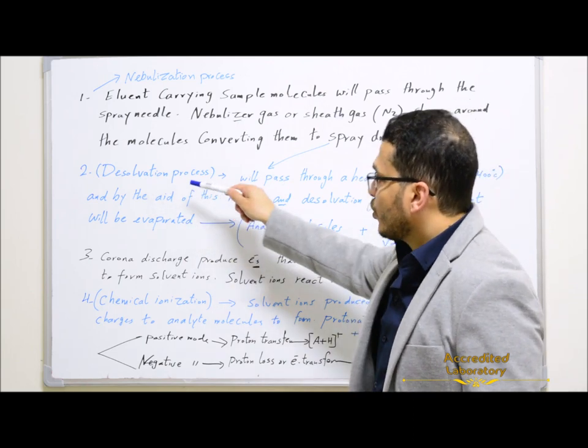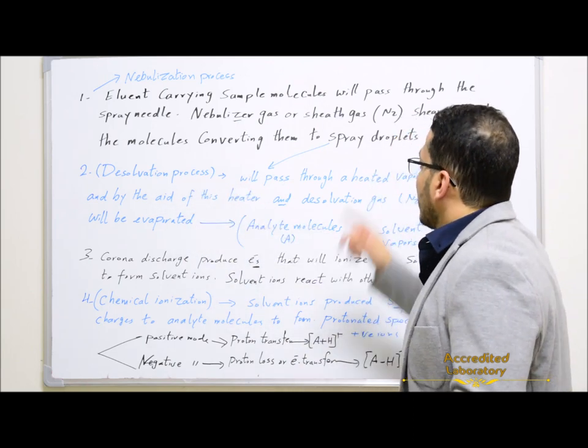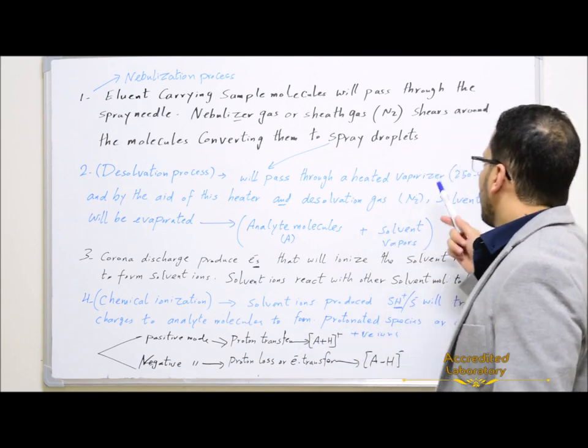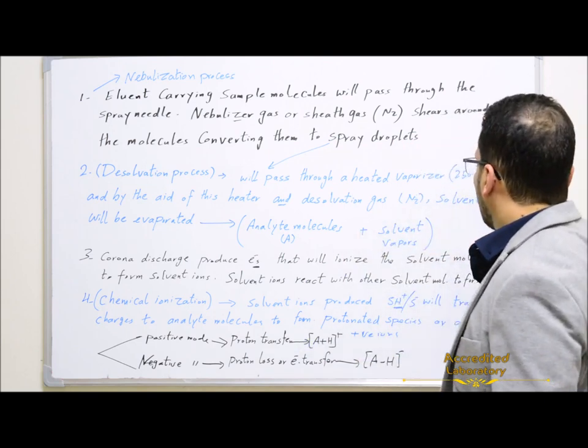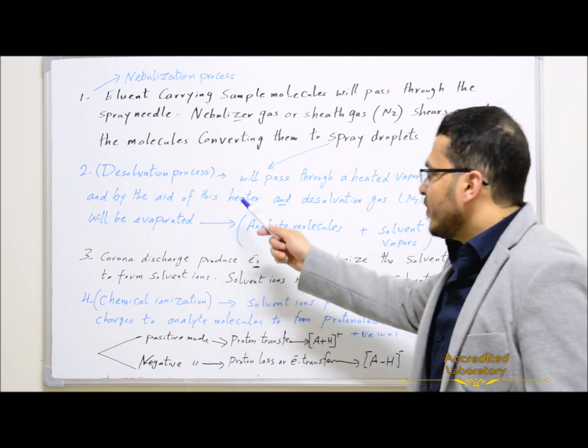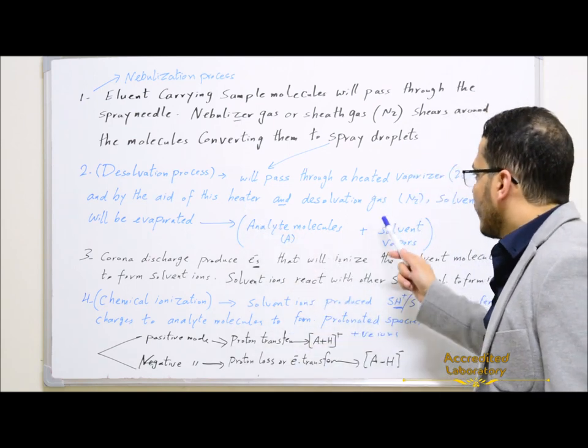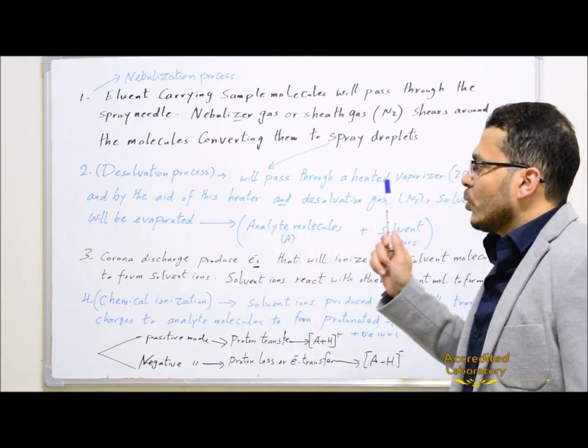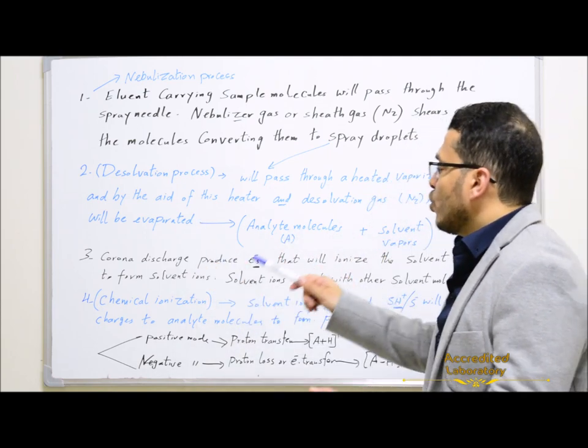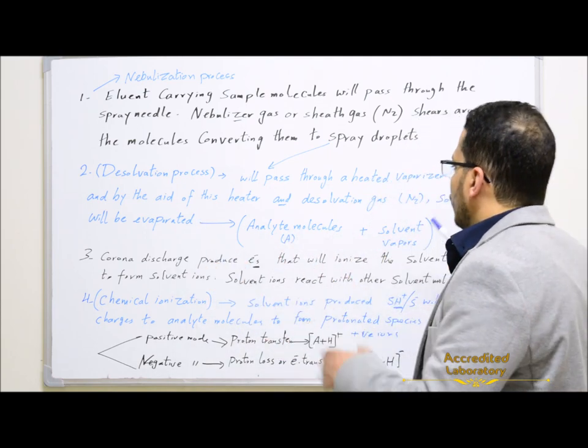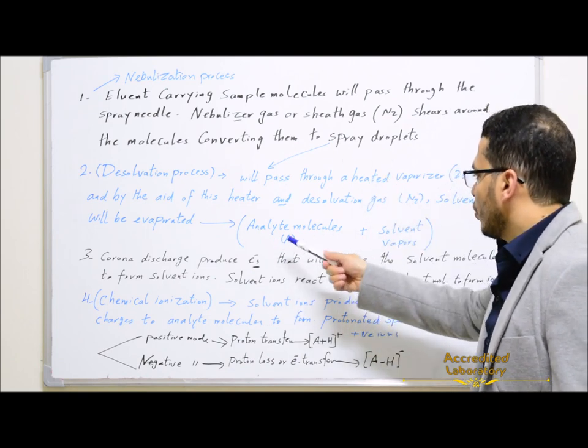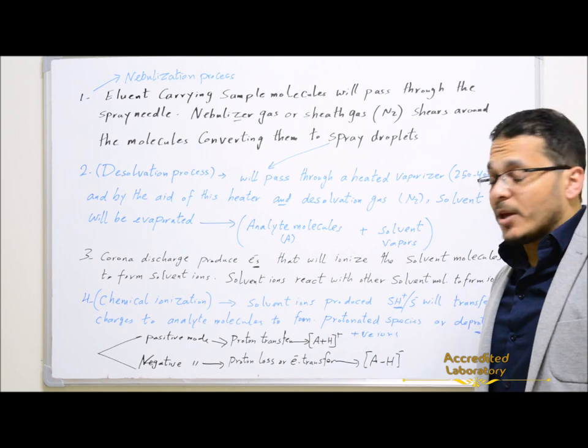After that, the desolvation process: these spray droplets will pass through a heated vaporizer at 250 to 400 degrees centigrade. By the aid of this heater and desolvation gas, solvent molecules will be evaporated, and these spray droplets will be converted to analyte molecules and solvent vapors.